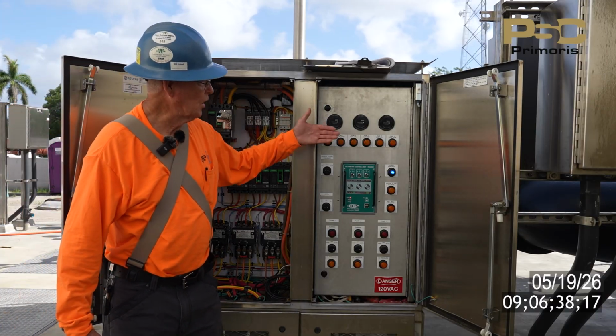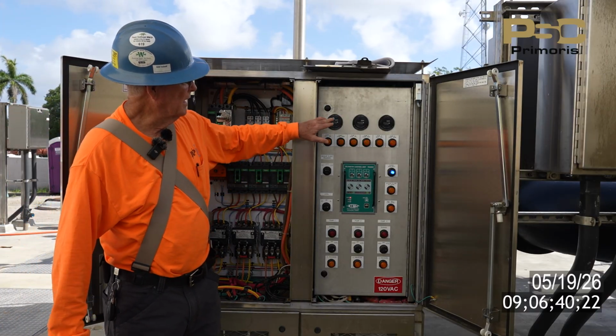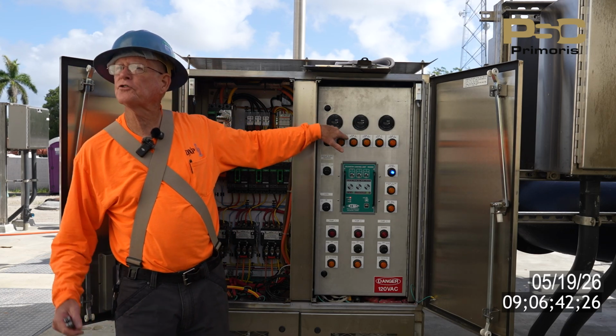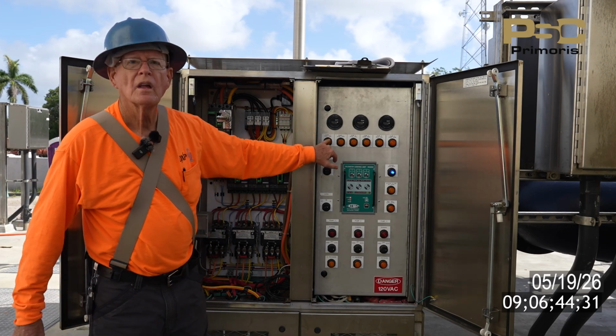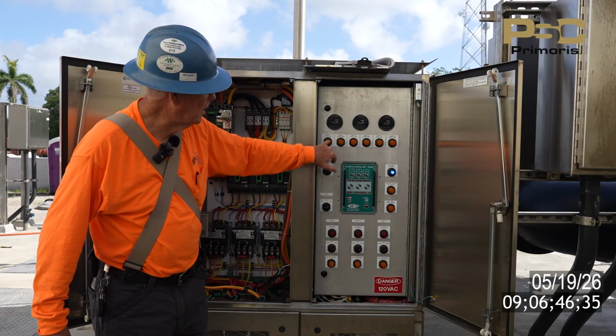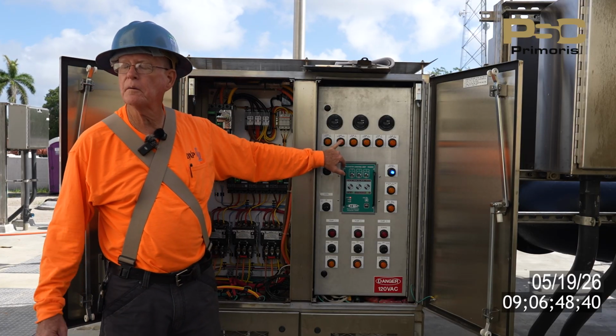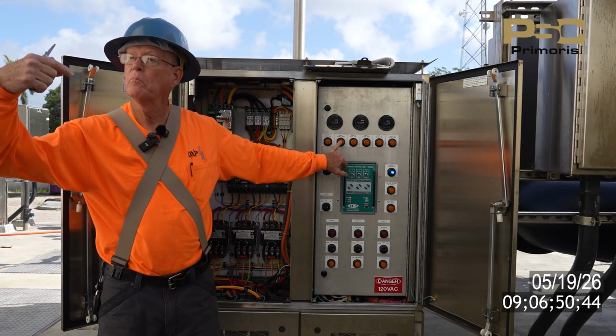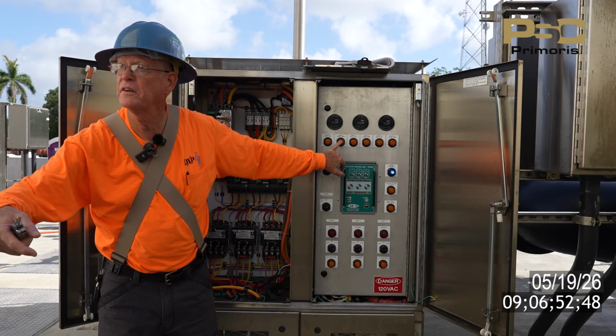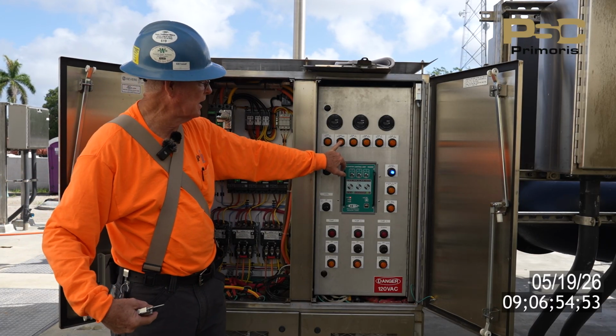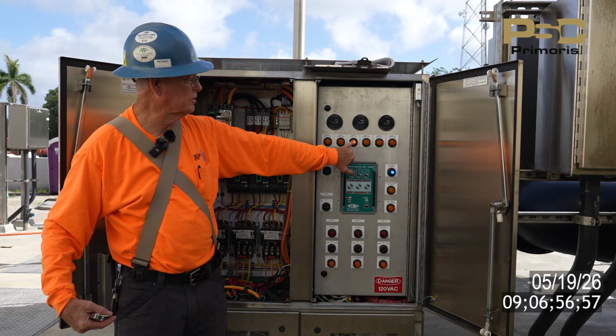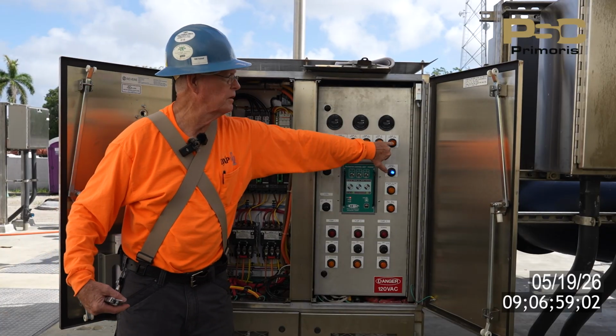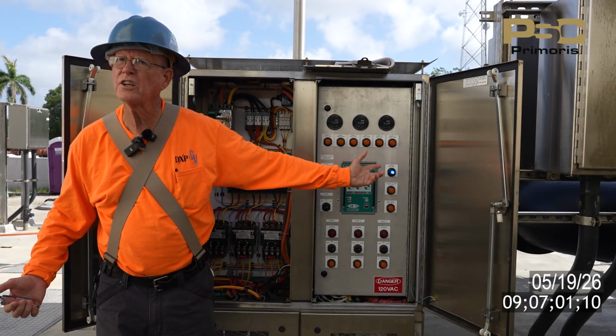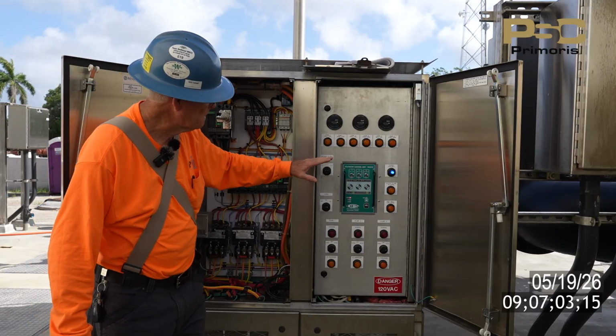Then over here on the control side, I've got elapsed time meters for each individual pump. I've got a seal fail and an overtemp light for each pump, independent of each other, so it's all for itself. And they're push-to-test, so if you want to make sure the lights or signals are working, you just push the test.